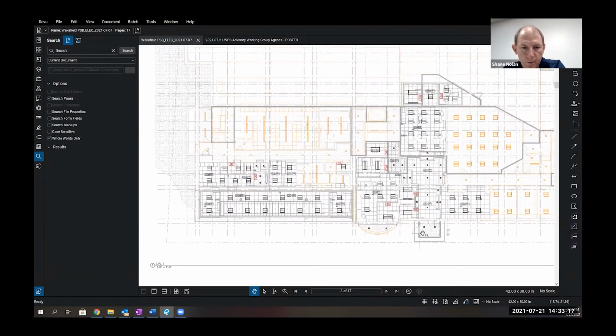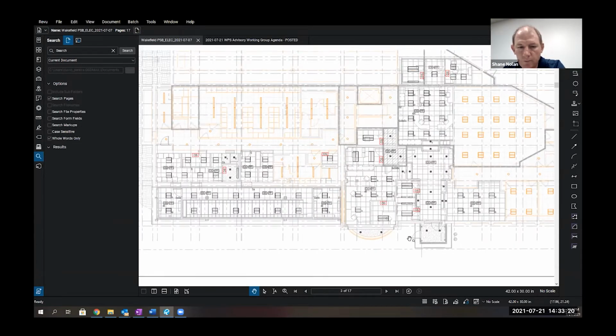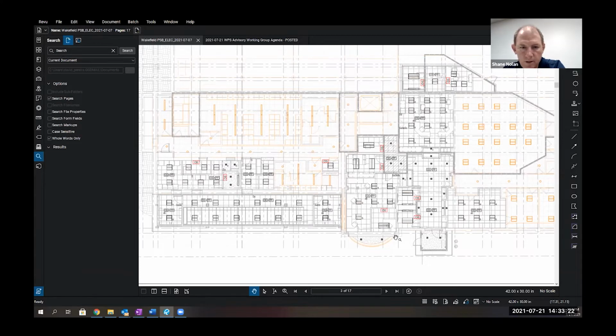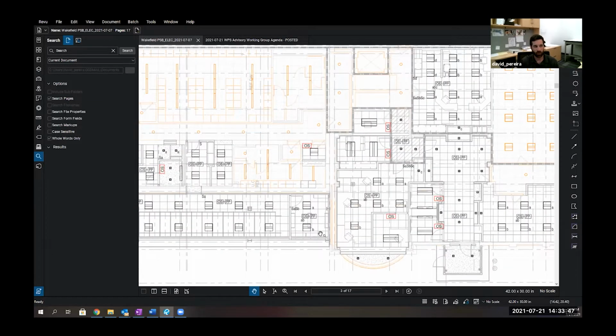I think we'd agreed that local control was okay the last time we went through the electric. Yeah, it's an older lighting control system, and I see no advantage to utilizing it here. With one exception, exterior lights, we're going to use it because it's going to be time clock photocell. So with exception to the exterior lights, all these individual rooms will have local switching, occ sensor, and daylight harvesting.